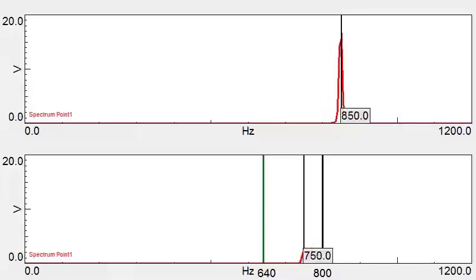Let me pause the acquisition here. You can see that the incoming signal is 50 Hz above the 800 Hz bandwidth. The signal on the bottom graph is being mirrored 50 Hz below the 800 Hz bandwidth at 750 Hz.